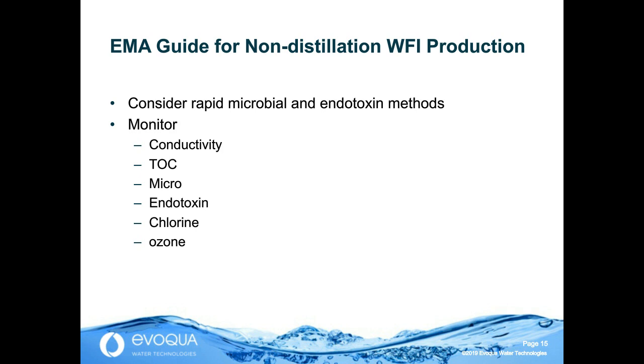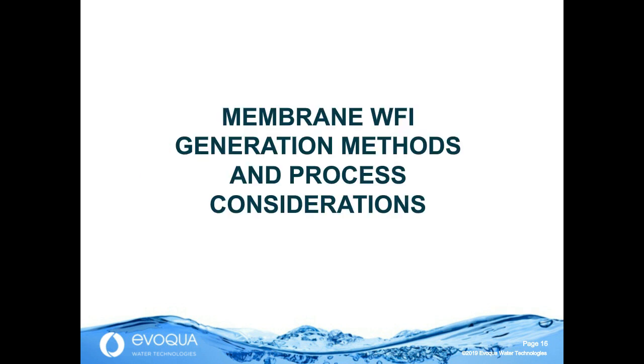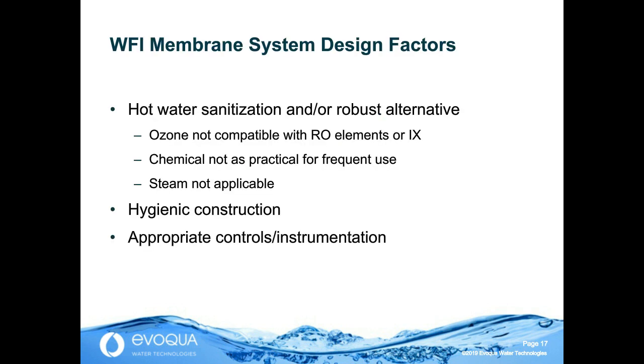If we now look at considerations to put these systems together, in a WFI membrane system, I think that hot water sanitization should be a requirement or a robust alternative. However, from a practical point, what is robust in generation equipment? Chemical is. And chemical has been proven to be able to work decades ago, but it's not as effective as heat, as automated, as verifiable, not as practical for frequent use because there's typically greater membrane damage from chemical than from heat. Steam is not really applicable to membrane systems, so hot water by default is by far the most effective method and I think appropriate for these systems.